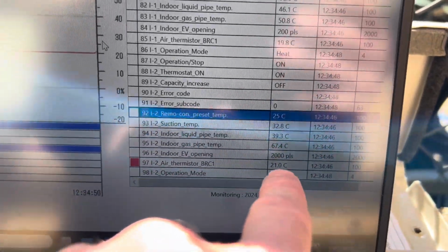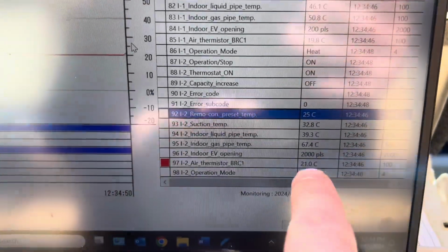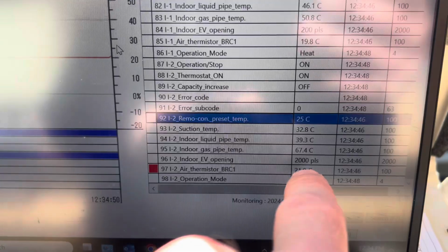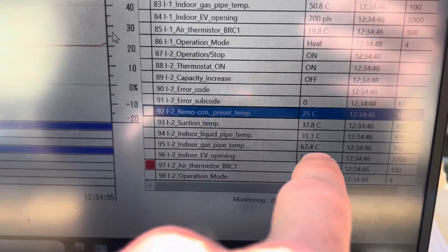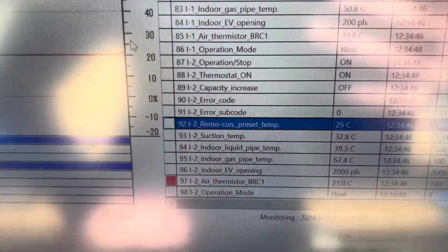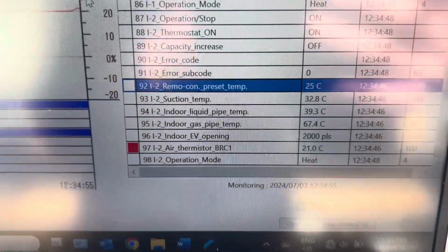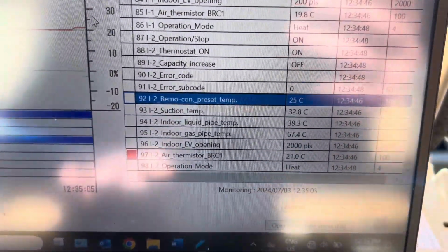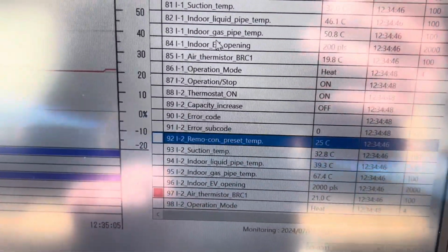All right, because what I'm seeing, Jesus. All right, so what we can see here, so our space temp's going up. It's now sitting at 21 degrees. What we can see though is my LEV pulse is basically fully open, right? So inlet gas pipe temp's 68 degrees or 67 degrees, which is pretty good. And liquid pipe temp's 39 degrees, right? So that's making, I'll throw the screen grab up of what I was getting before, but my liquid line was saying 42.